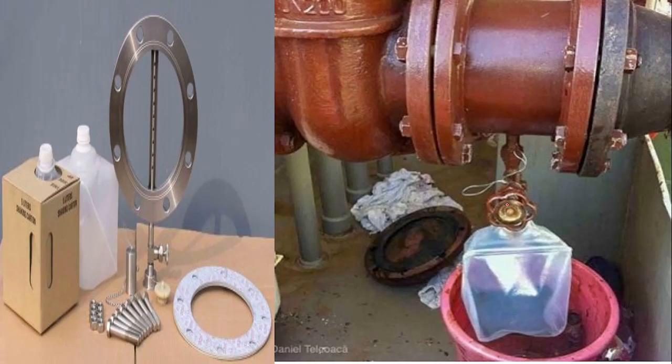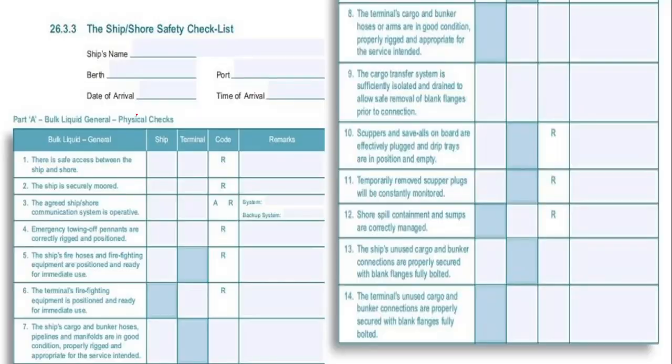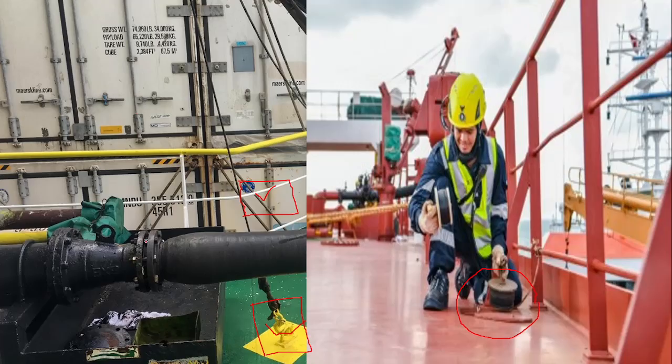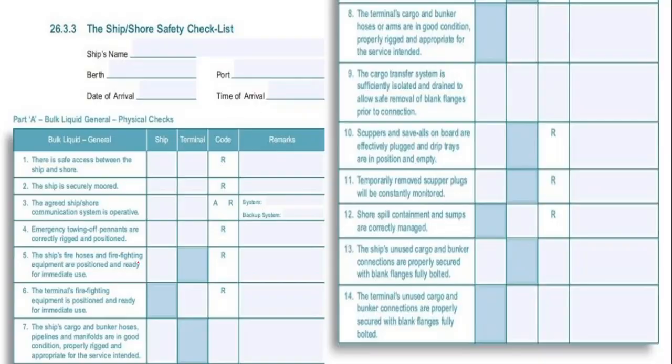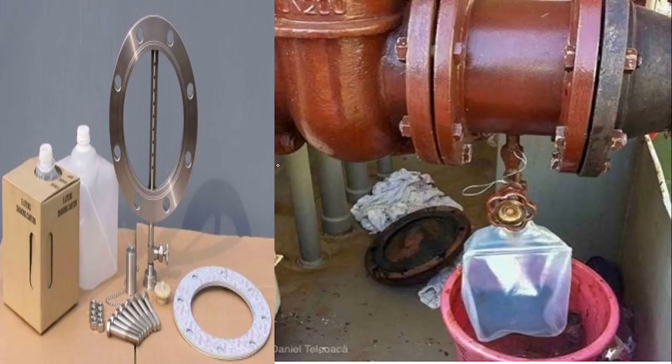If not, then you have to use this. So where will you put this? You will put it here, in between here. After that, the oil will flow during the bunker from here. The oil is flowing from here, and here a hole is provided, and through this hole the oil will go down and come down here. You have to put this here, and you can adjust the flow by this valve. So this is called a drip sample collection flange.